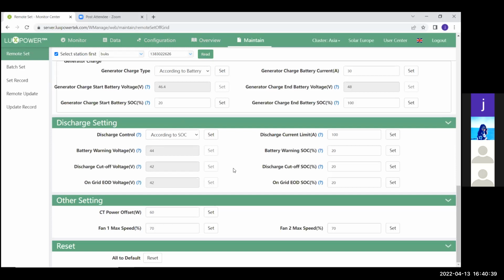Now, discharge settings. Here, it's also quite easy to set. Discharge settings, you can put it against voltage or SOC. Voltage is for batteries that can't communicate, and SOC is for batteries that can communicate. This side here is if you put all your parameters in volts.